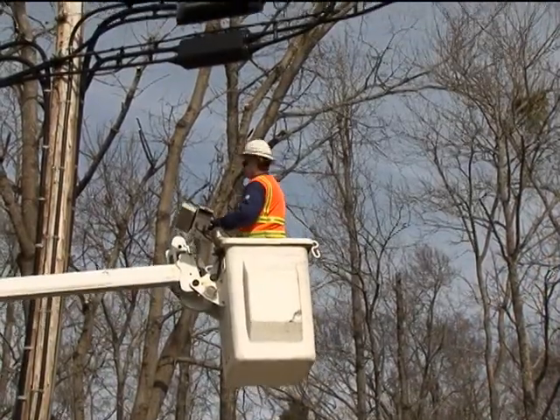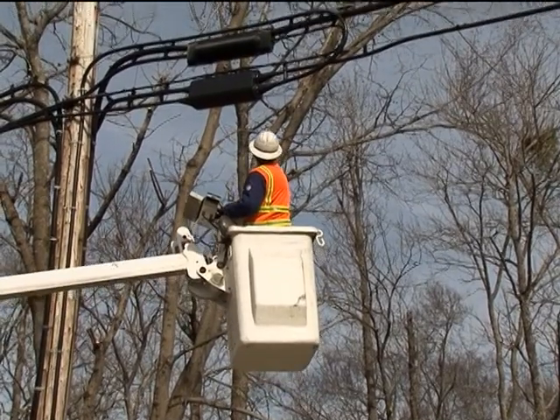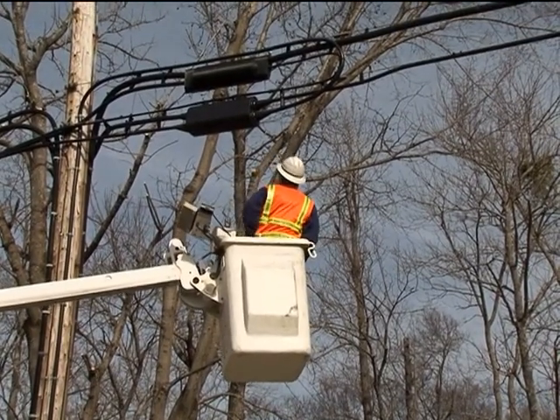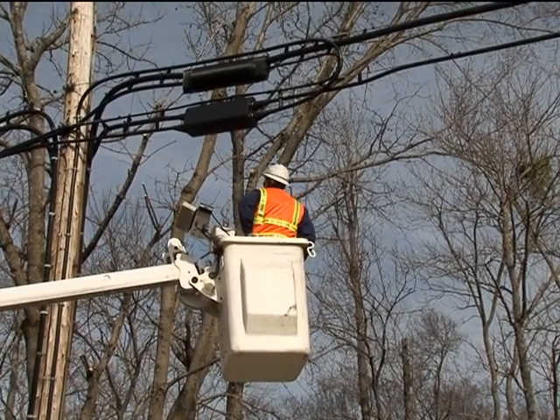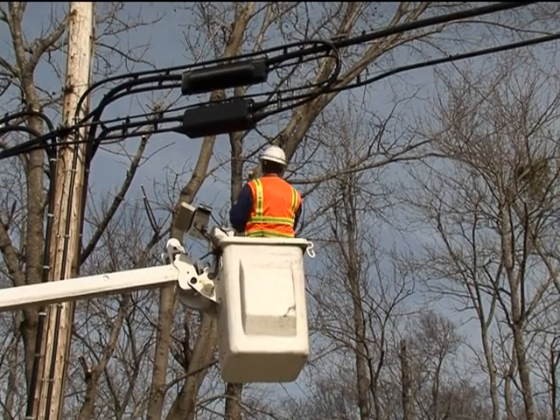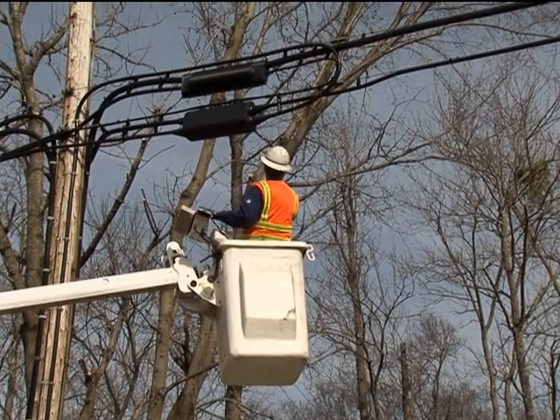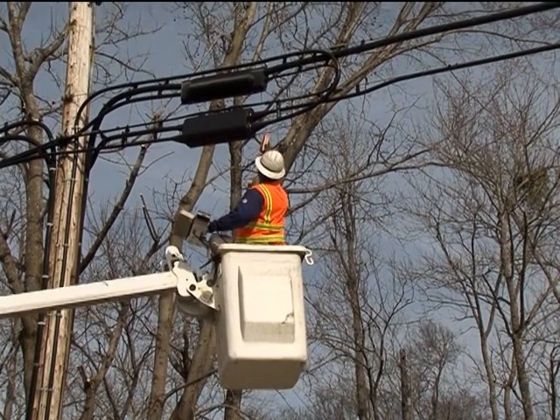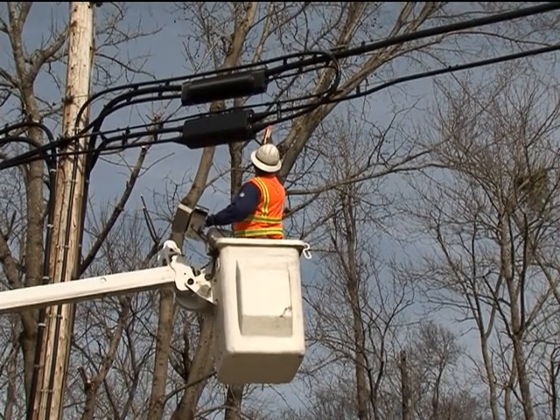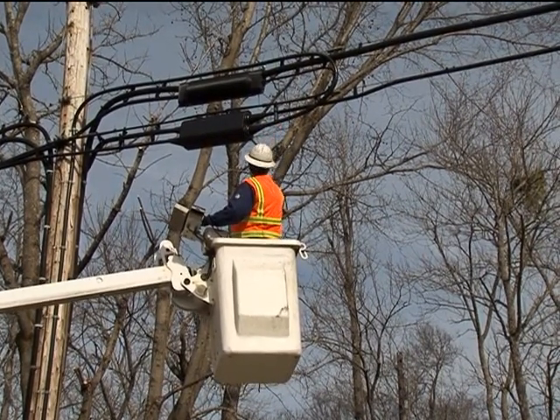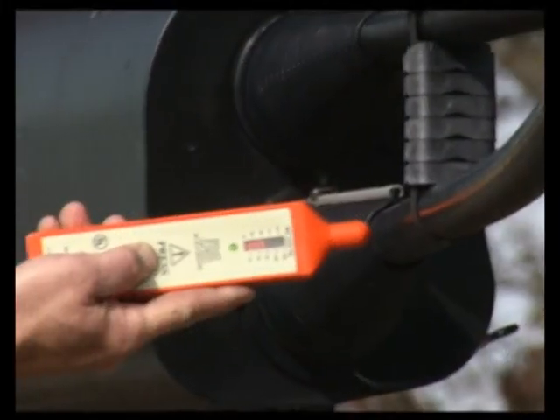When working aloft, a technician can make use of the shielding effect of the cable or strand being tested. As seen earlier, a grounded conductor will shield a technician from being coupled to an electric field. Keeping this in mind, you should always approach the cable or strand to be tested from below. The cable or strand will serve as a shield for the technician.